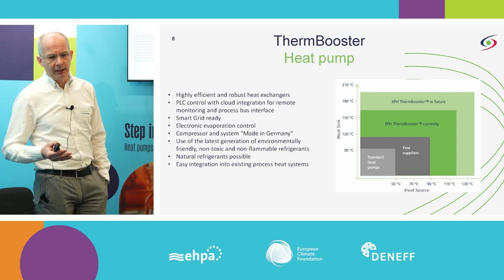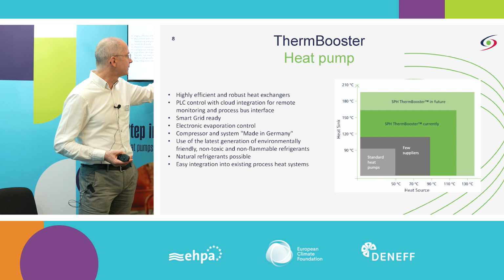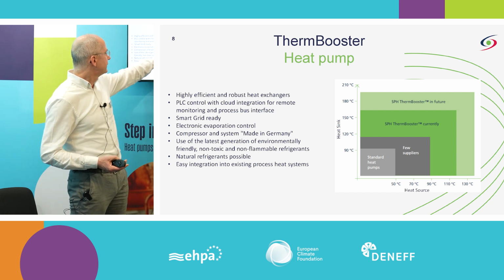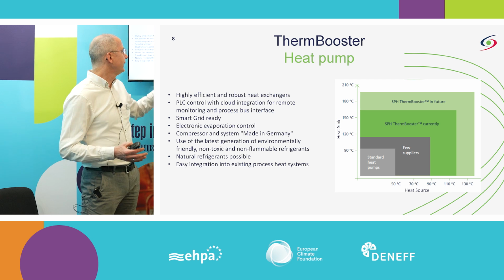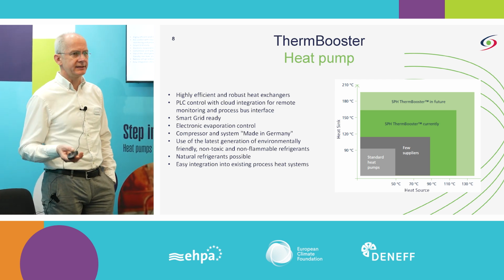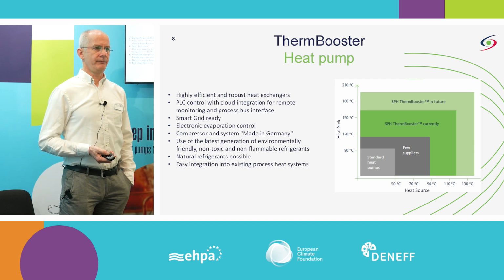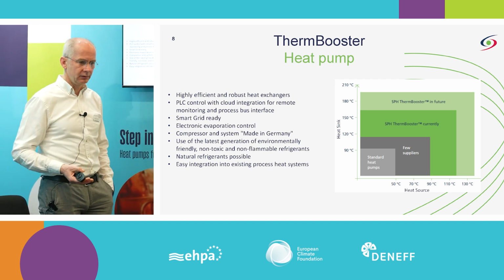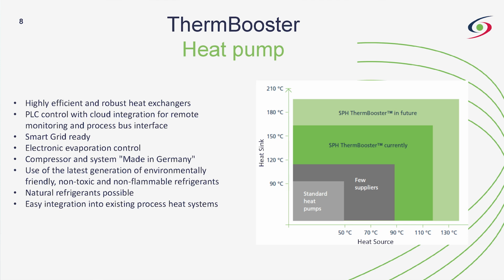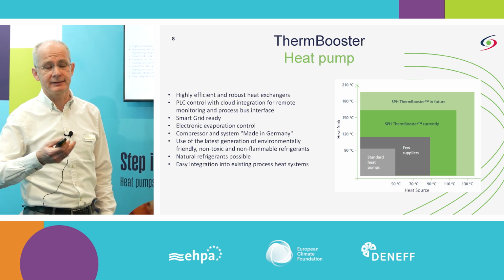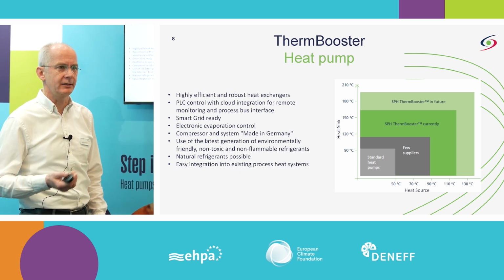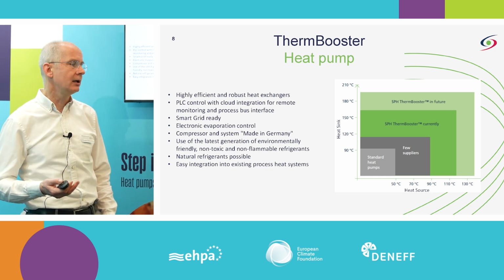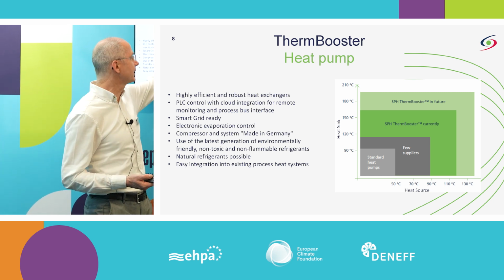So if we look onto this chart here, or onto this table, you see the temperature range which we can achieve currently is at 160, 165, depending a little bit on if we are producing steam or hot water. So with steam we can go to 160, with hot water to 165. We can go higher. This is not an issue. Currently we are limited, at least when we use HFOs, by the fact that there is no HFO currently which can go higher. If we go to natural refrigerants, we also could come higher with the heat pump.